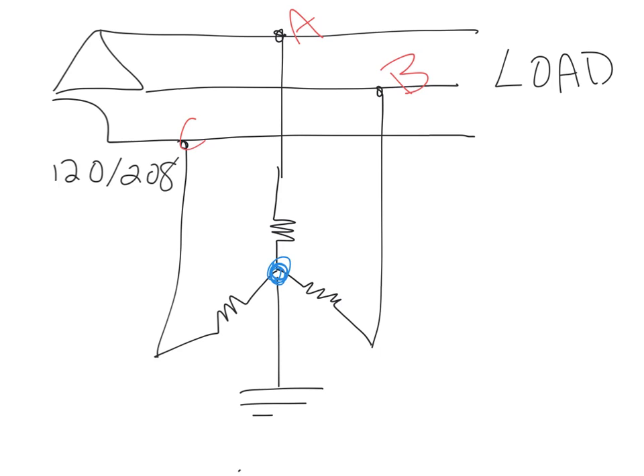Now where this device is kind of neat is if you think back to your Y-Delta theory: if we have a ground fault, let's say up here at point A, that ground fault simply means current is flowing to ground. Well, if we were to draw a line to where ground is, ground is right there. By doing that, by making that or by it shorting to ground, what's happened is we have now made the star point the same point as line A.